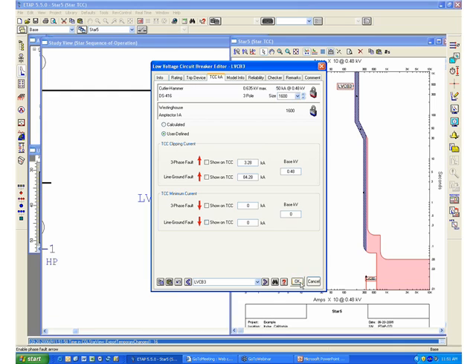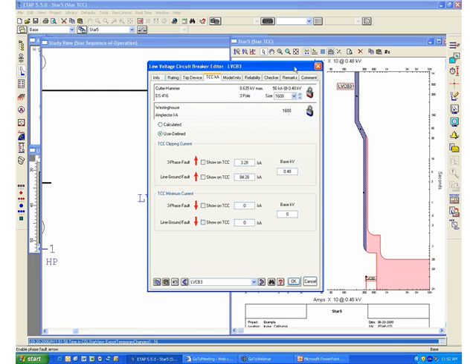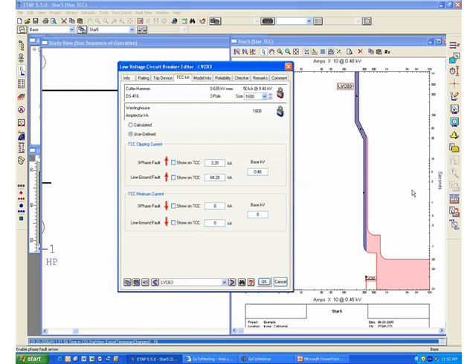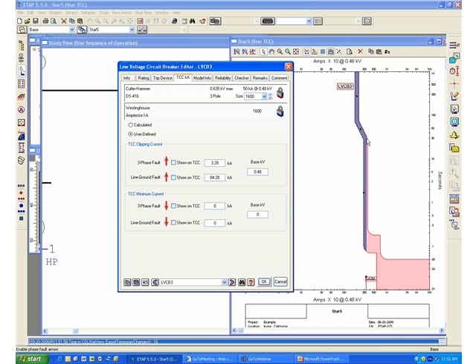We can observe on the screen right now the difference between the instantaneous setting time, which will be 0.05 to 0.1 seconds response, versus the much longer time on this long-time setting of this low voltage circuit breaker.